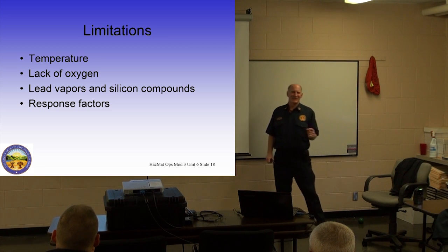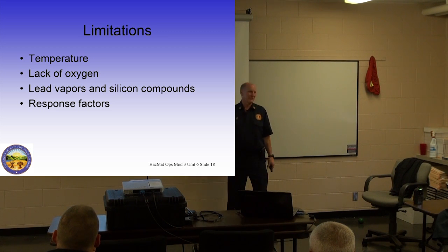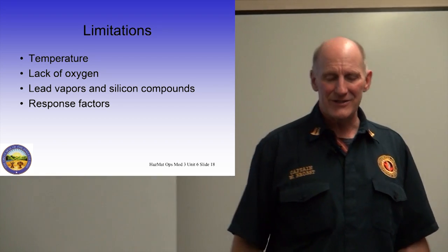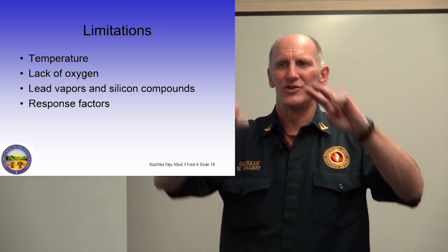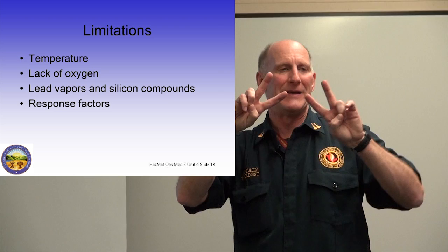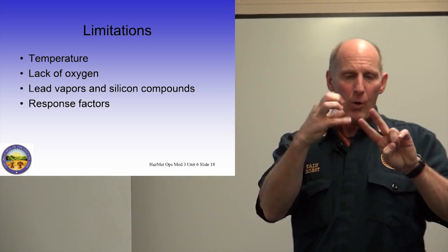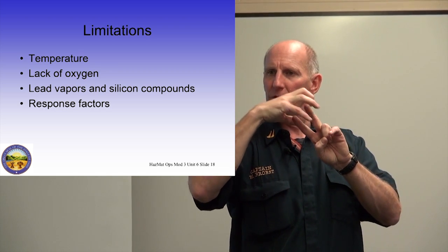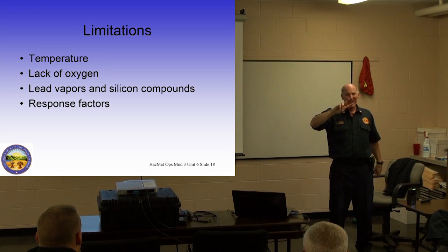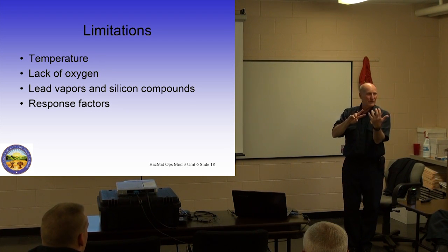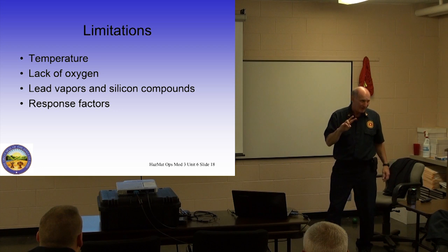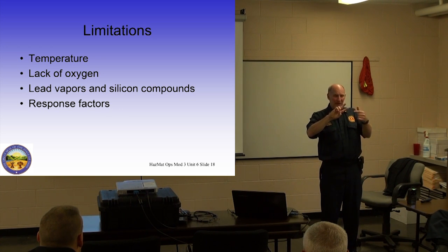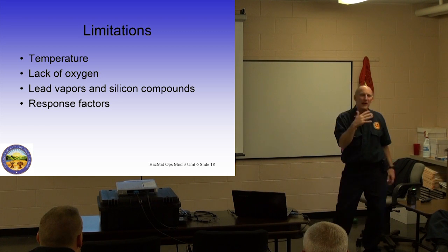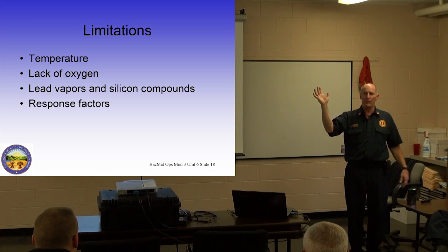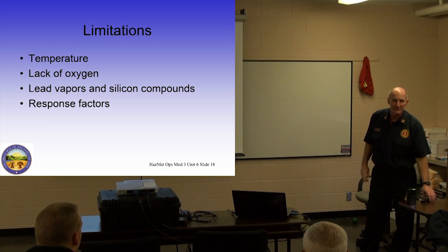The LEL sensor, it's got the same inaccuracy. In order for the LEL sensor to work, it's called a Wheatstone bridge. There are 2 little filaments, like light bulb filaments in there. One of them burns in a perfect atmosphere at the same speed all of the time. The other one burns in whatever atmosphere is coming through it. Well, okay. If the atmosphere has something flammable, this little filament burns brighter, the electricity is measured, and it says, hey, there's something flammable in the air, and we get LEL readings.